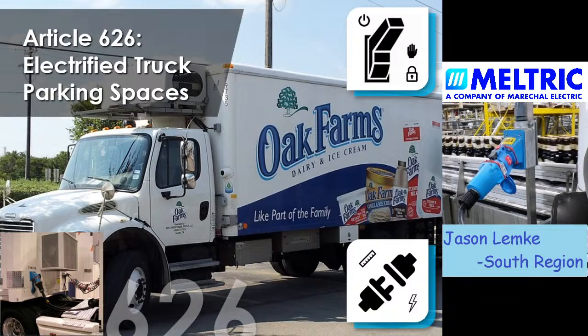Appreciate that. So before we go into the next portion of this presentation, I really just wanted everybody to know to pay attention in the National Electric Code when you're specifying your disconnecting means, particularly if you're going to use a plug-in receptacle for that disconnecting means, because you've got other additional requirements of the disconnecting means that your plug-in receptacle may not meet. So ensure that when you specify that device for a disconnecting means, you include other things that are required. Maybe it's switching, maybe it's accessible, maybe it is the ability to be lockable. So if those are the things you're looking for, just make sure that your plug-in receptacle, if you're using it as a disconnecting means, has those additional features as well.